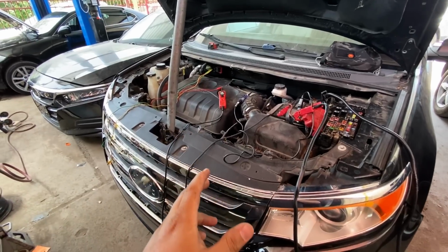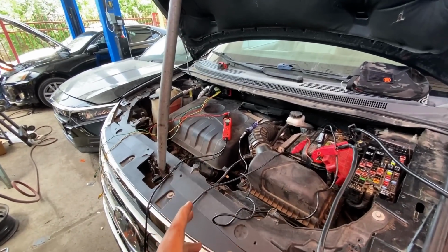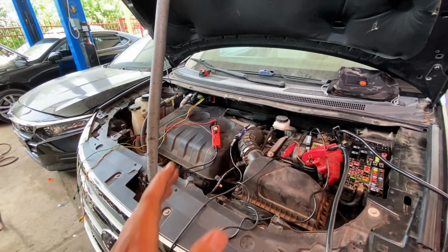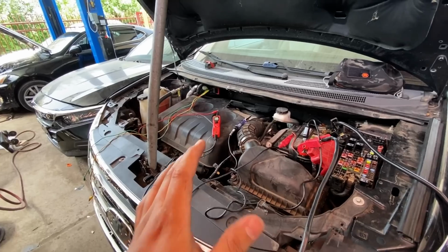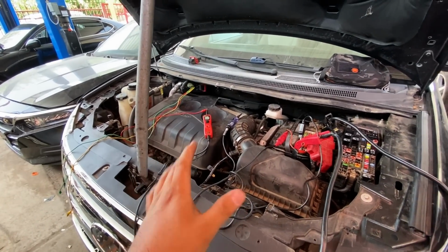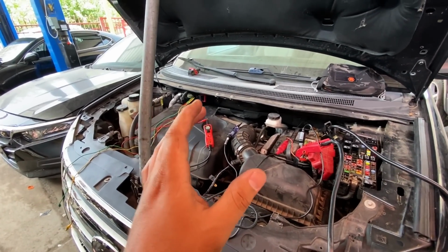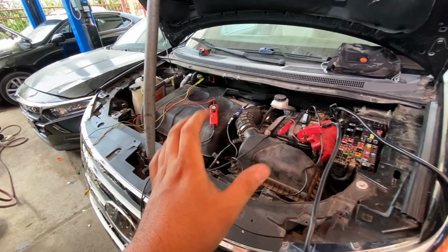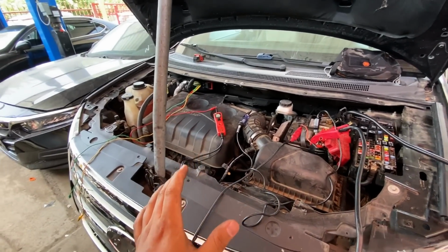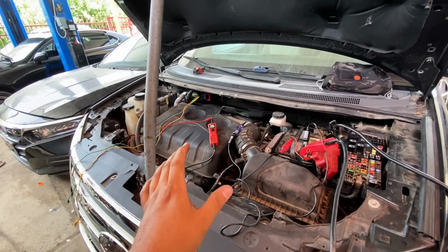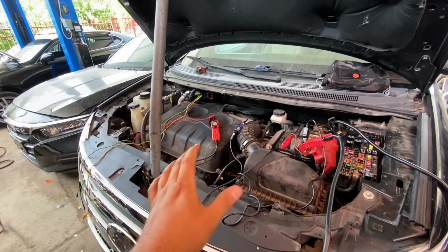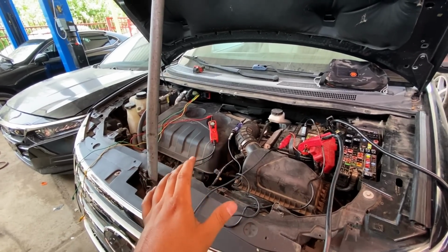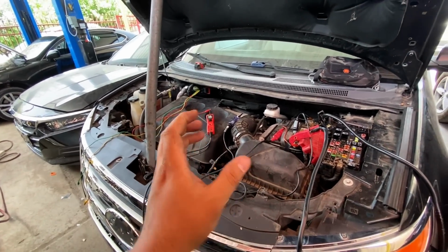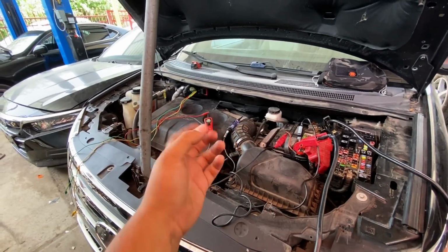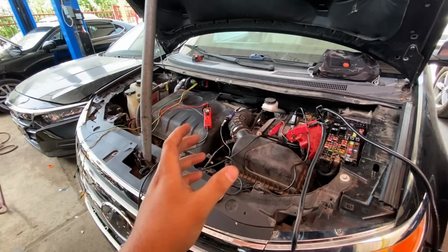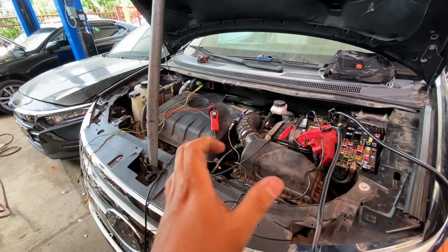Now that we've verified we don't have a reference voltage at our engine computer, next we need to check whether we have a shorted sensor bringing down our reference voltage to ground. I'll say this is highly unlikely, because we have 3 different reference voltages, and for all of them to be taken down to ground is unlikely unless internal to the computer all 3 are shared. So I really don't think we have an issue with a shorted sensor.